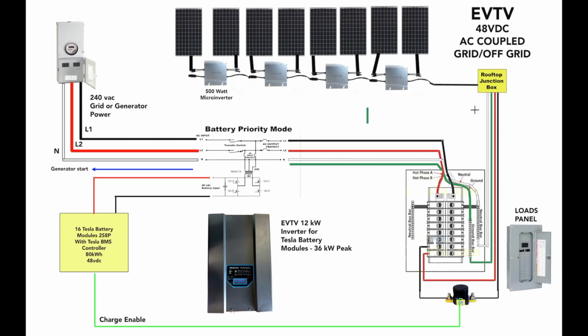So this is an AC coupled system, versus a DC coupled system. We would normally have the panels and then MPPT charge control, and they would connect here at the battery before the inverter. In this case, in our AC coupled system, we connect where this is. Now, what are the advantages? Well, as I said, you eliminate a lot of equipment. We don't need a special charger for a battery. We don't need an MPPT charge controller. We don't need a combiner box. We don't need to bring 500 volts DC down from the roof.